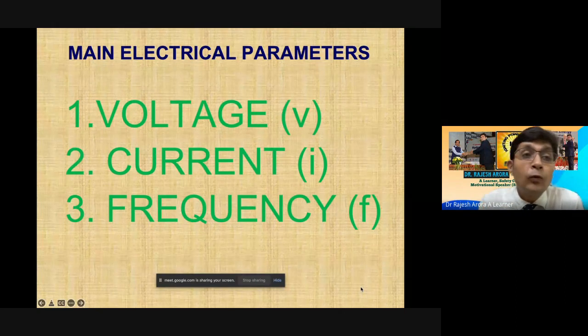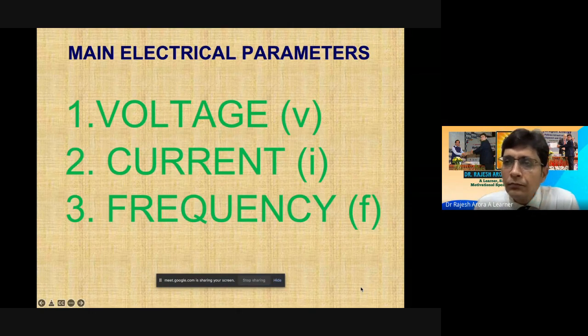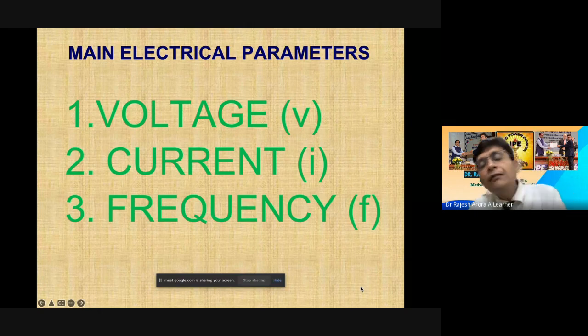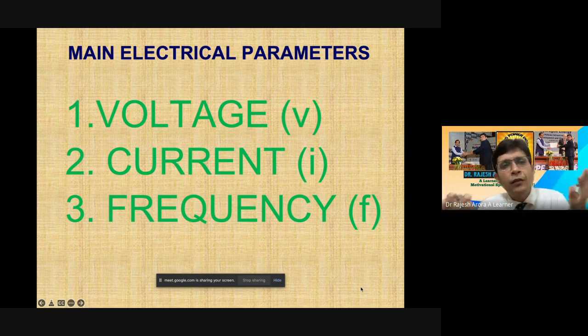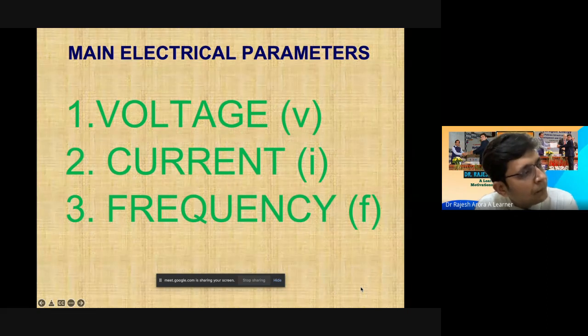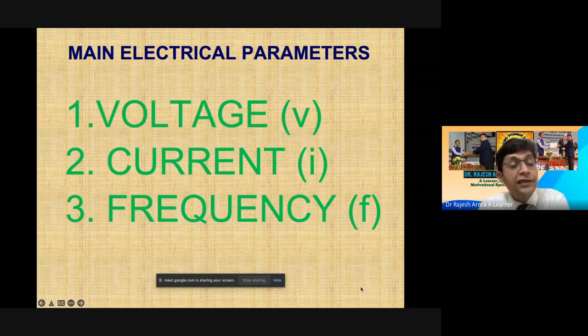For that, you must have good knowledge about short circuit calculation. When I say frequency, it is basically related to the harmonics generated by the use of electronic gadgets at home, in our industry, in our substations, solid state devices. We assume 50 hertz frequency, but actually it is not only 50 hertz. There are so many harmonics. With harmonics, your total harmonic distortion increases, your power factor decreases, and with that decrease in power factor, your current requirement increases, and more heat is generated in the area you are working in because of these harmonics.